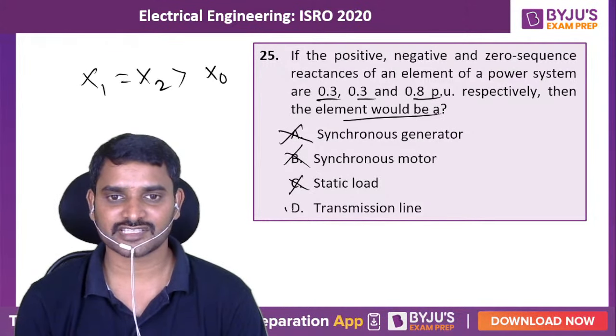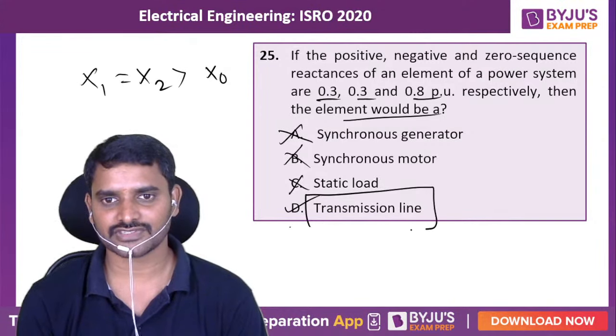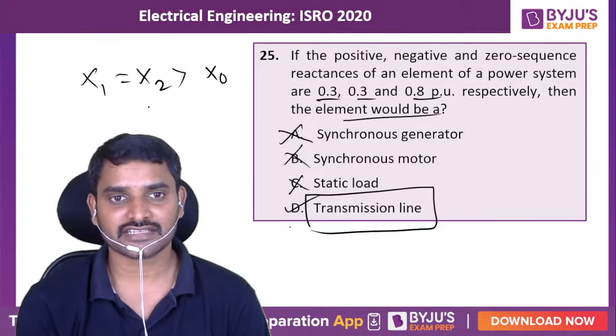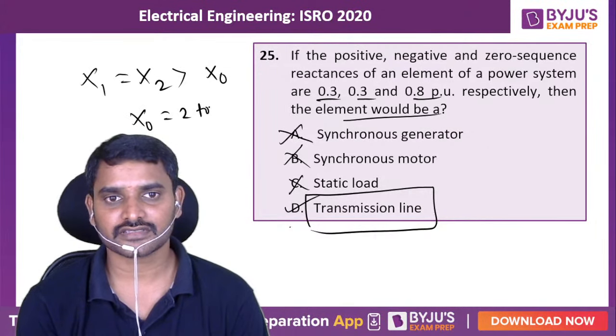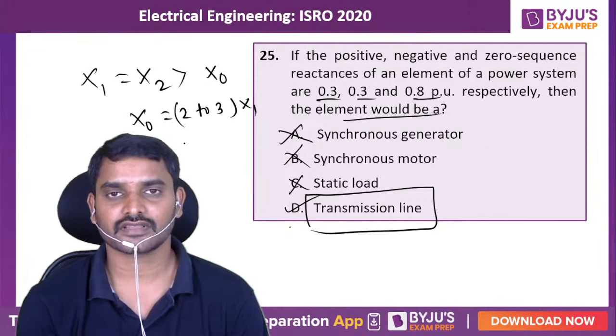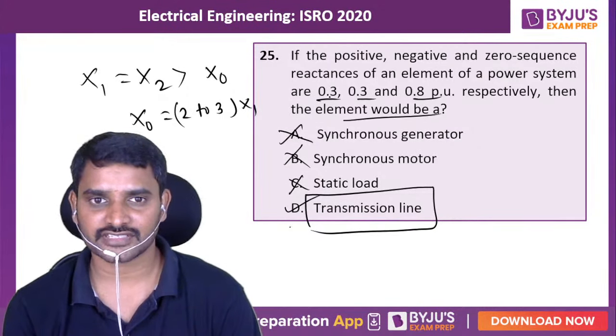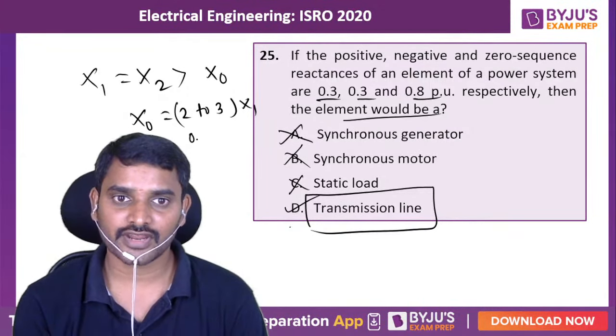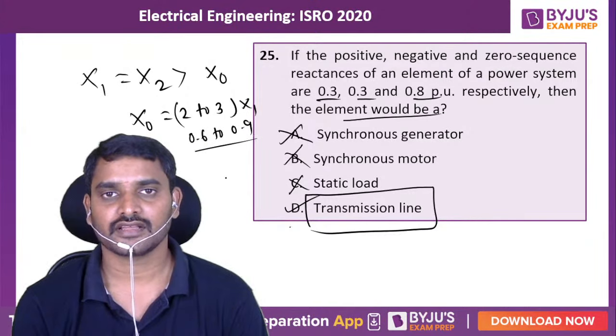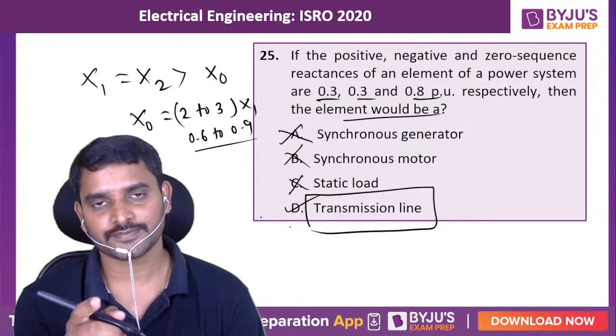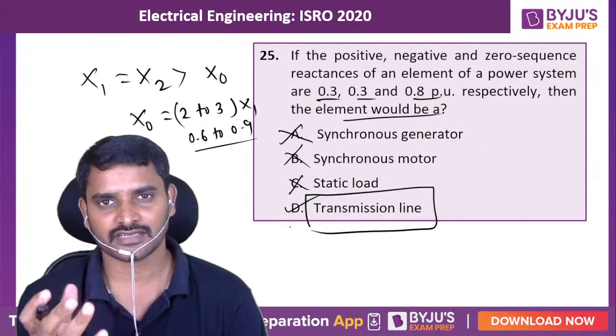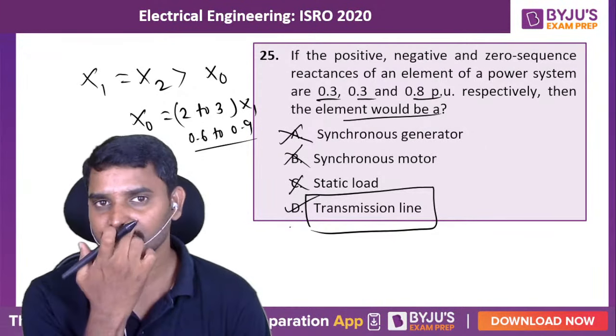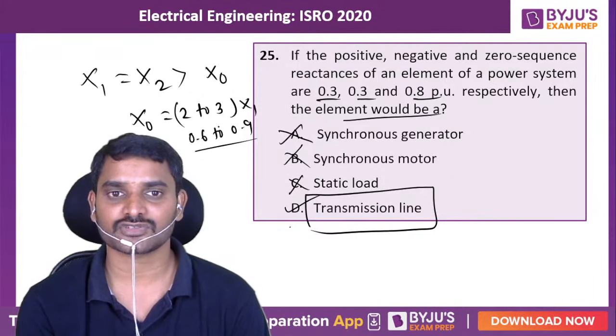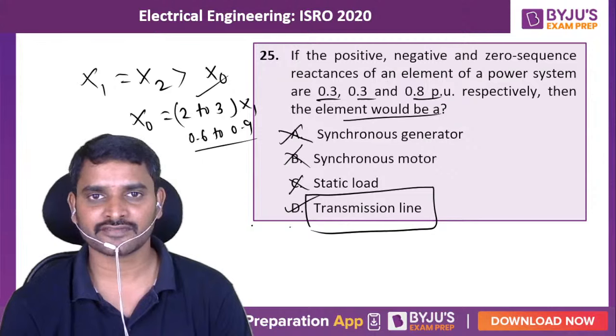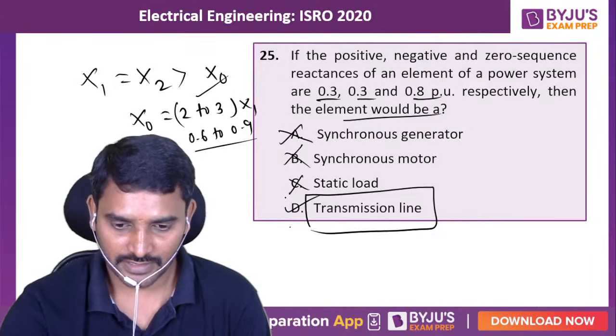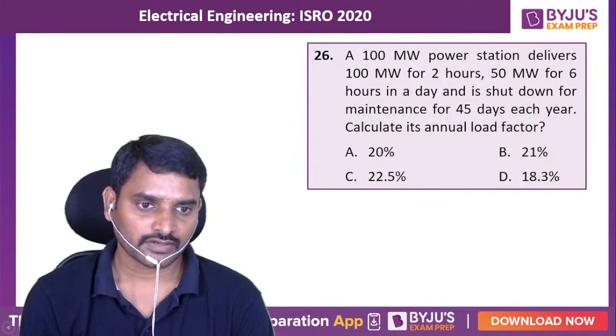The only option is the transmission line. There is one statement also: generally, zero sequence reactance is around 2 to 3 times the positive sequence reactance. So 2 into 0.3 is around 0.6, and 3 into 0.3 is around 0.9, so 0.6 to 0.9. Because the ground return is also going to be included, and at different soil conditions the reactance is going to change, hence it is taken as 2 to 3 times. So the transmission line will be the proper answer. Very good, Ashok. What is the next question?